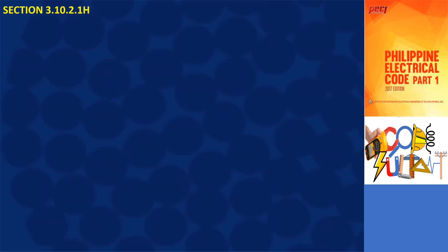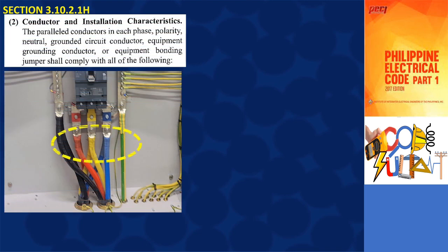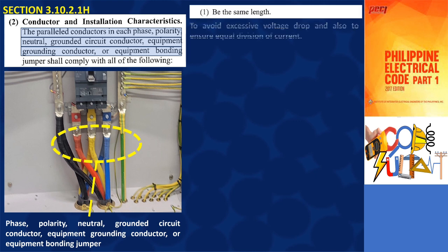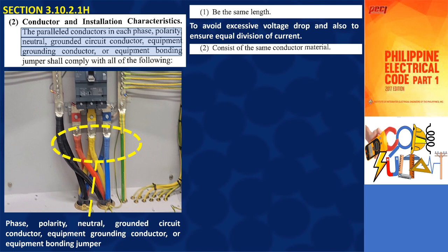To install conductors in parallel, the paralleled conductors in each phase, polarity, neutral, grounded circuit conductor, equipment grounding conductor, or equipment bonding jumper must comply with all of the following. First, be the same length. To avoid excessive voltage drop and also to ensure equal division of current, different phase conductors must be located close together to attain the requirement of having the same length. Second, consist of the same conductor material. It is a requirement that all conductors of the same phase or neutral must be composed of the same conductor material.